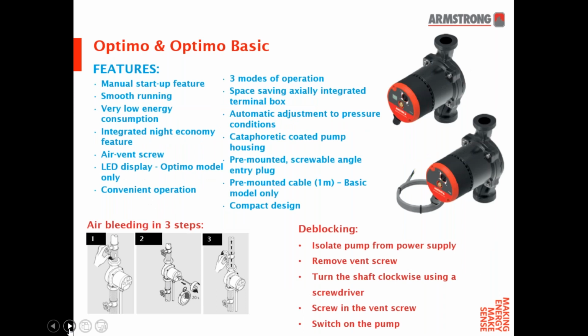So looking at the features for both the Optimo and the Optimo Basic, one thing I haven't mentioned, I apologise, is that the Optimo is the first picture, the upper picture, and the lower image is the Optimo Basic. So both have exactly the same features, apart from two slight differences. Both of the models will have a manual startup feature. They both have smooth running and very low energy consumption, as they both have A-rated pumps. An integrated night feature, which reduces the energy. And one thing that installers seem to like is the air vent screw right in the middle of the face of the dial. We'll just go into that a little bit later on.